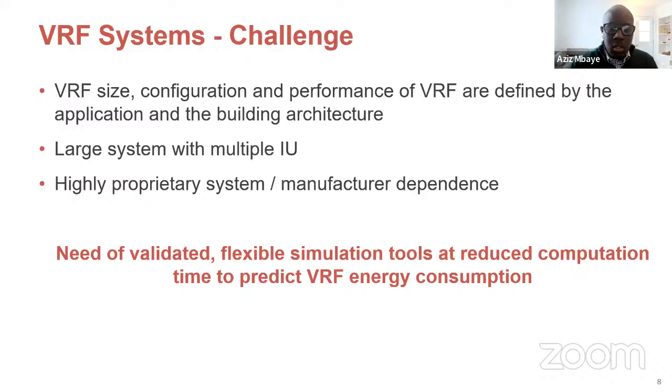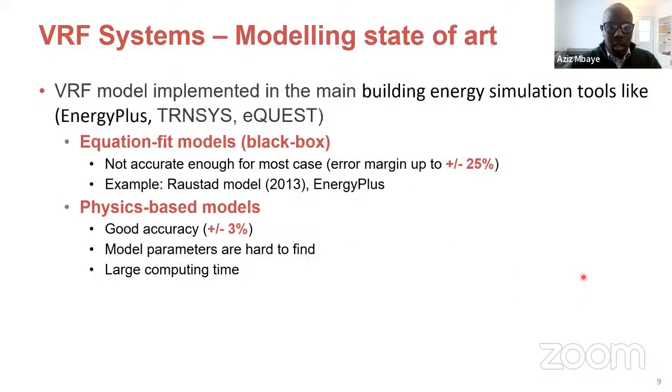So those are some of the reasons why, to support the development of VRF systems, to facilitate their design and to evaluate their performances, it is necessary to have a validated, flexible simulation tool at reduced computational time and open source, that will also help predict their energy consumption. And as of today, there are several non-proprietary VRF models implemented in different building energy simulation tools like EnergyPlus, TRNSYS, eQuest, and so on. And those models range from detailed physics models to equation-fit models with varying levels of accuracy.